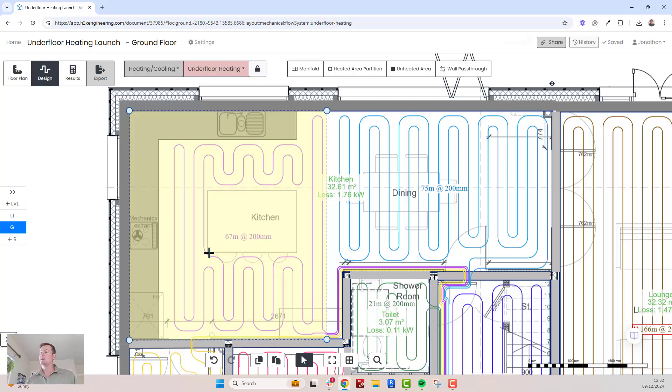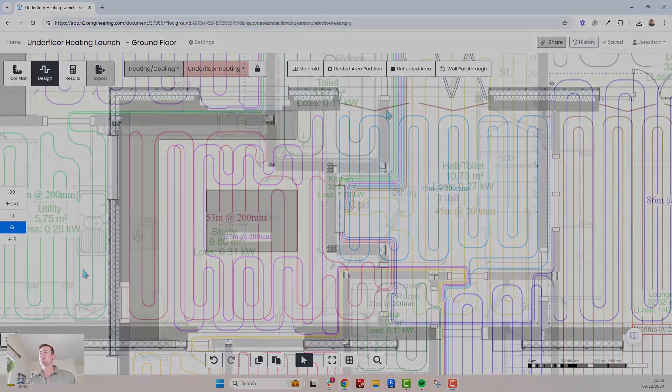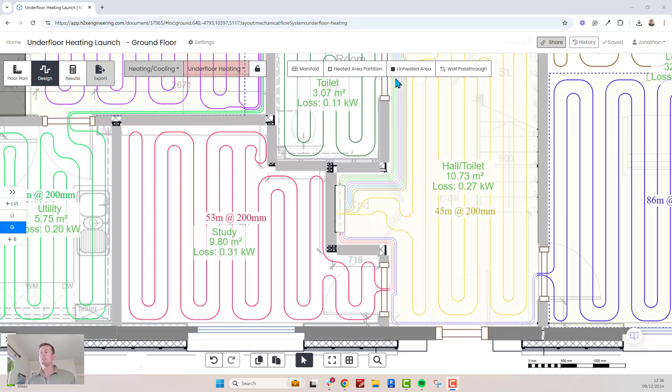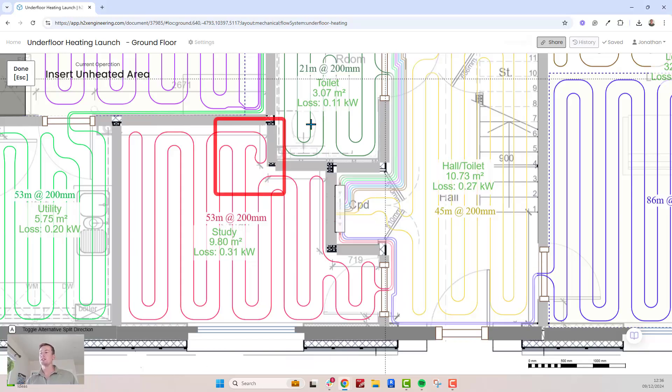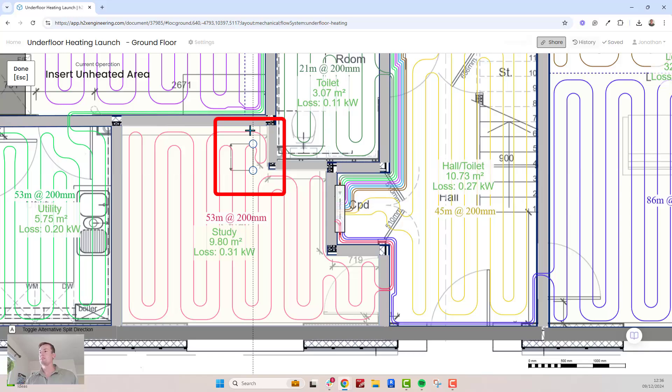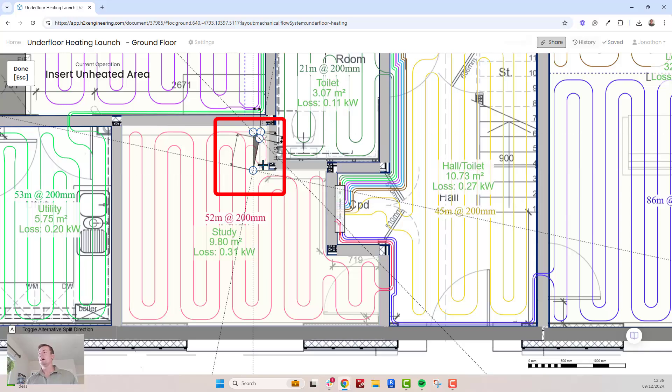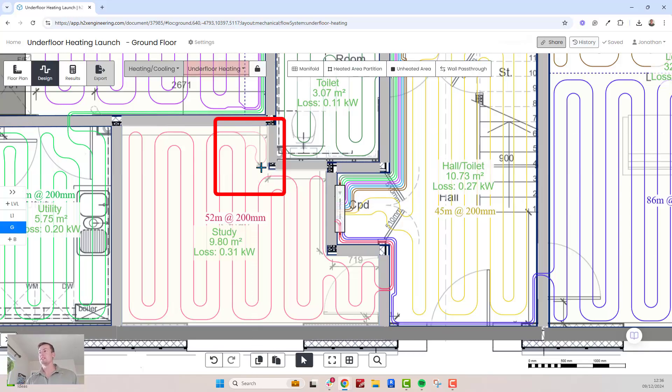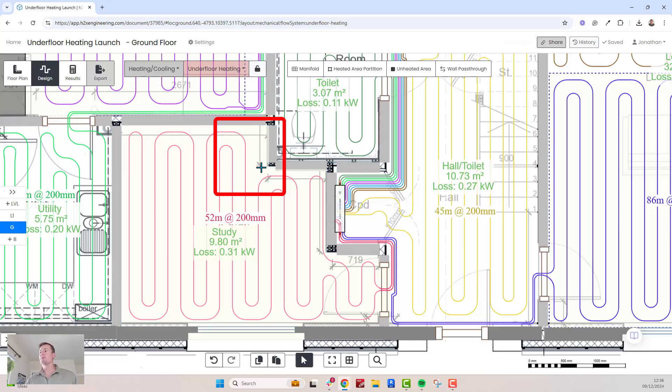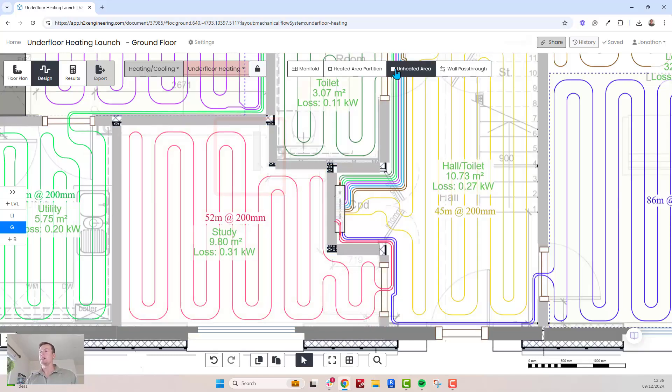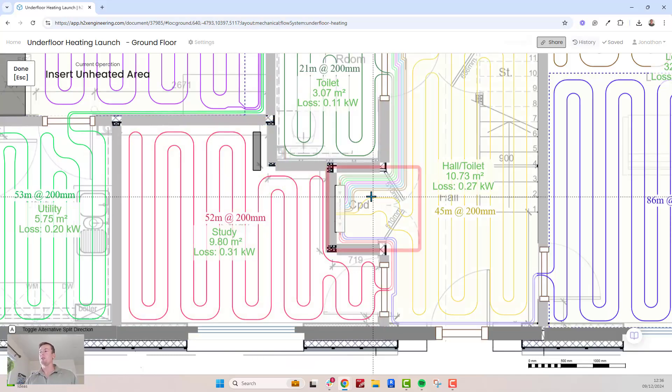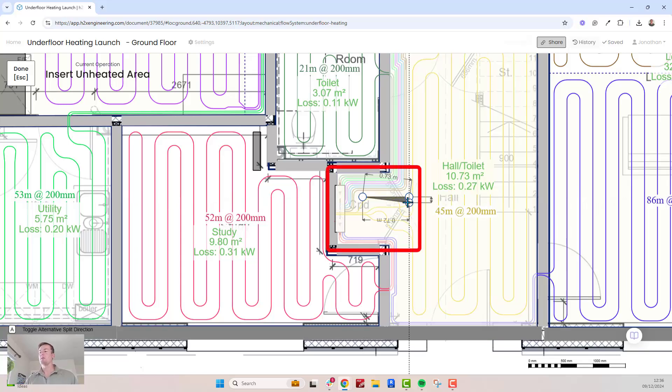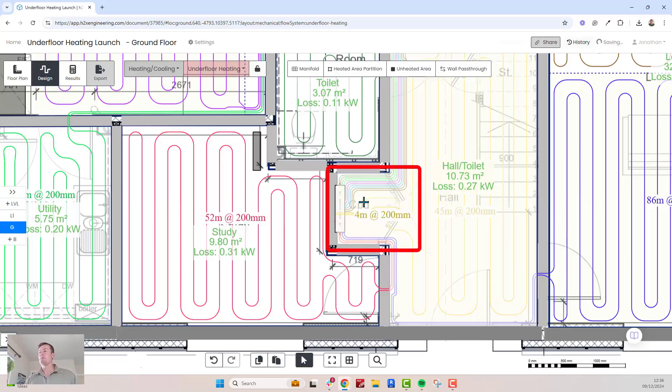The software doesn't have direct loop editing tools, but instead you can use unheated areas to give you flexibility whilst refining your design. For example, if you don't want the loop to extend into this part of the room, add an unheated area and it will update the loop to avoid it. You can also use unheated areas to straighten out loops, such as here coming out of the manifold.